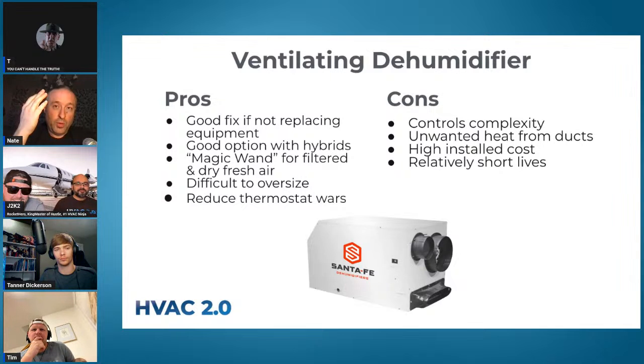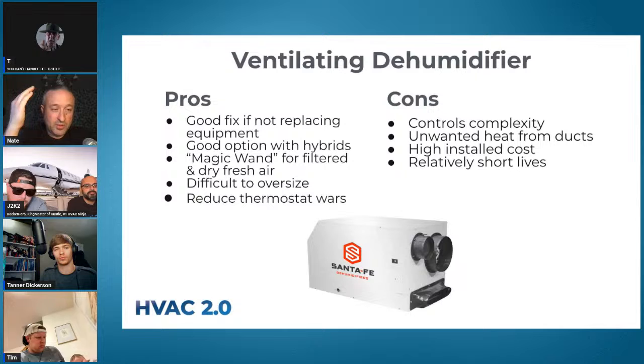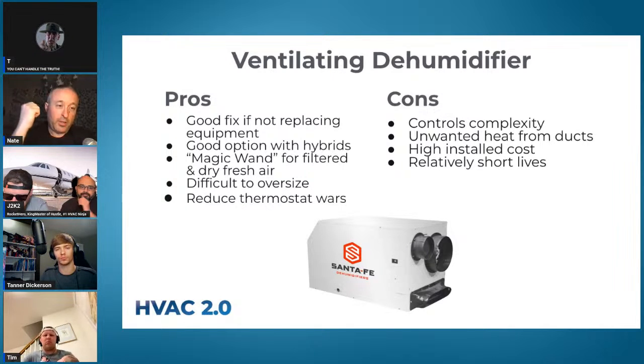We can do everything you want with about a $7,000 piece of equipment that has reheat, and you'll still need a cheap little dehu for picking up the slack when that happens. They do a small enough amount of work that the $250 units can last for 4 or 5 years instead of 1, 2, or 3.